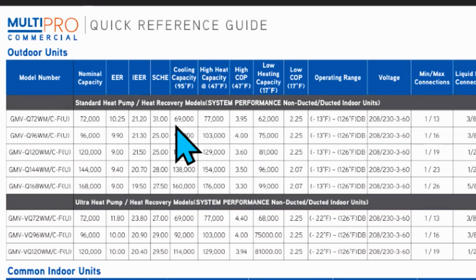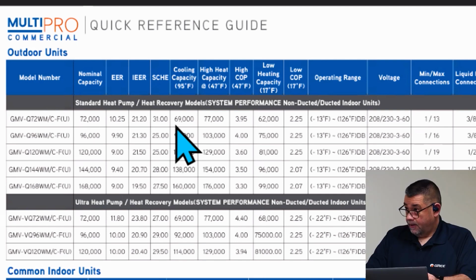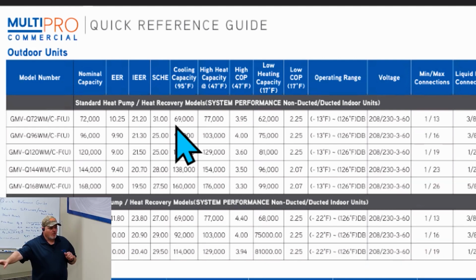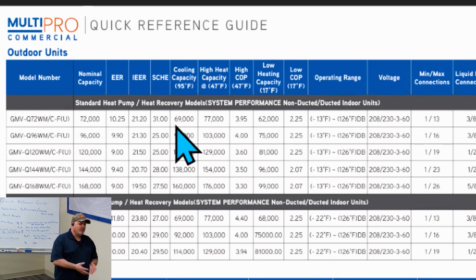So looking at those numbers, to me it looks like the best option for efficiency would be heat recovery. It's actually the best option for efficiency, but it's also best for office spaces where you've got one person that's always hot and one that's always cold - it gives them the ability to have one room in cooling and one room in heating. You can't do that with a heat pump.